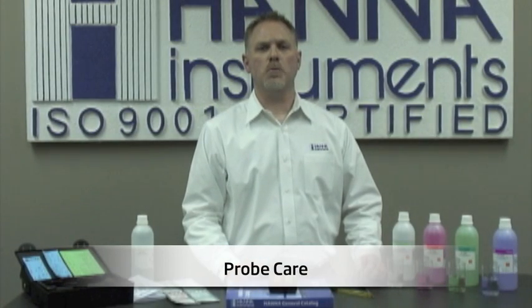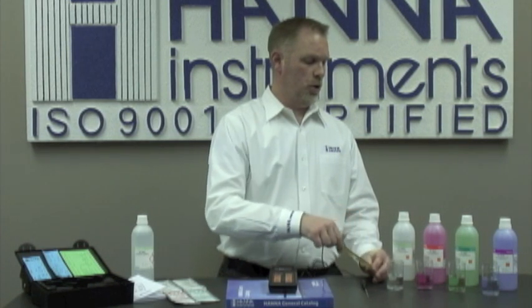Now that we've completed our measurement, it's time to put the probe away. We need to use some of our storage solution in the protective cap to maintain the condition of the probe. If you don't have storage solution, you can use any one of our buffers. If you happen to have drifting readings, it may mean that the probe is dirty and you might need to use one of our cleaning solutions.